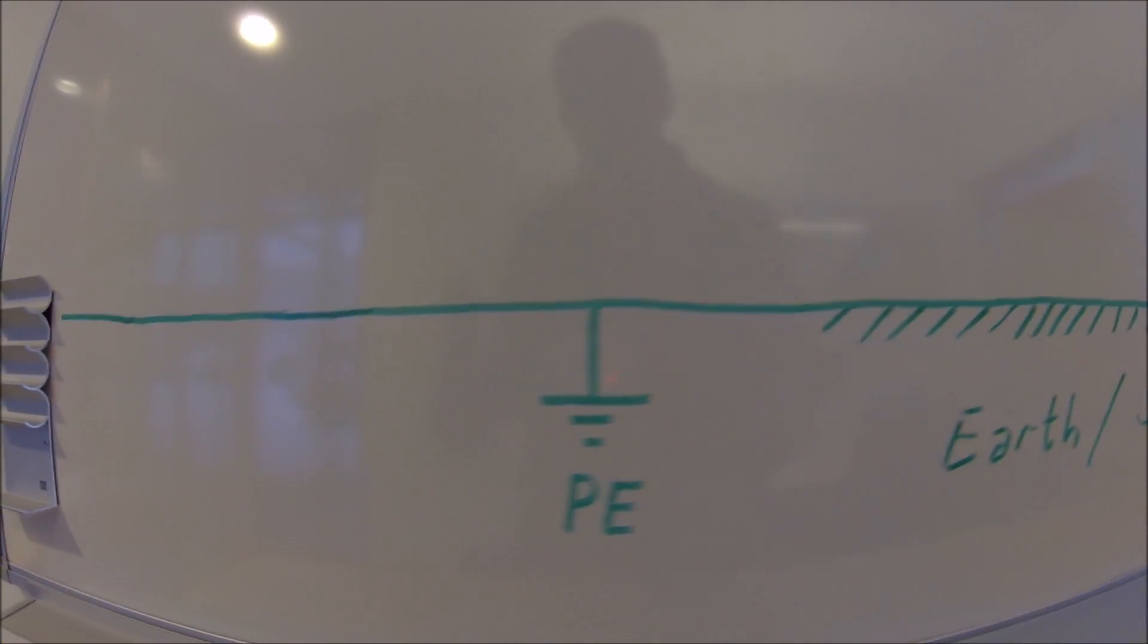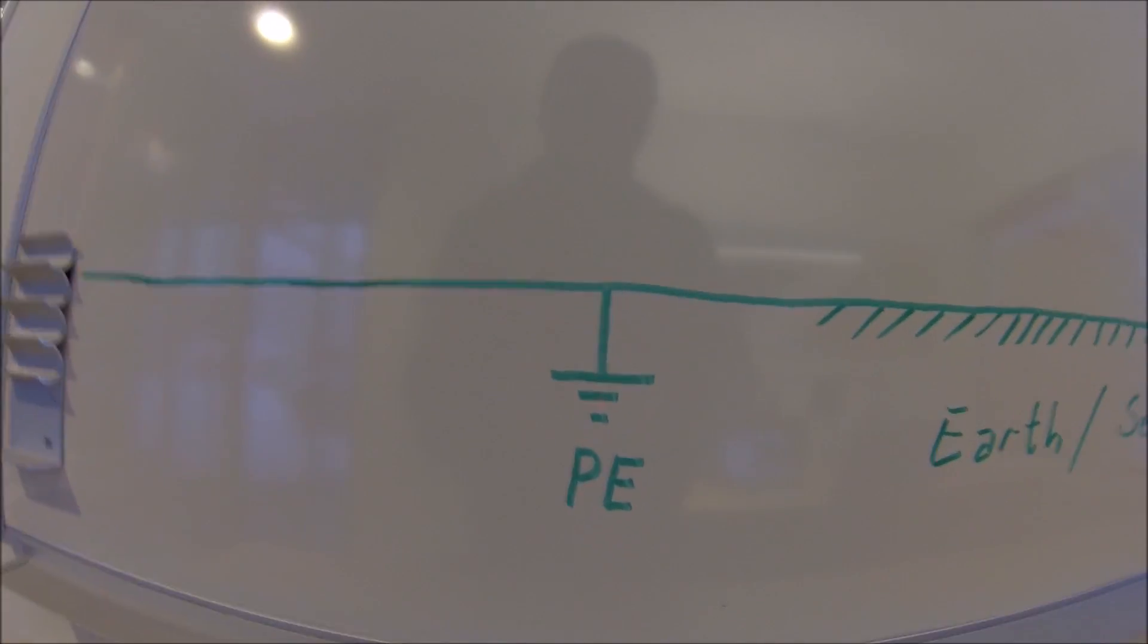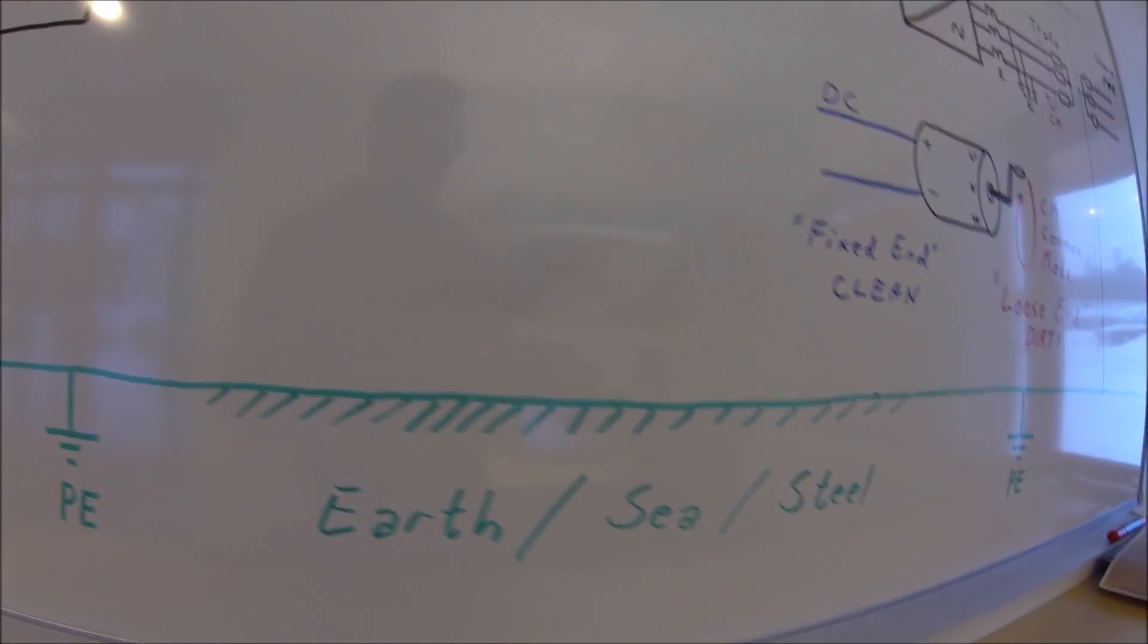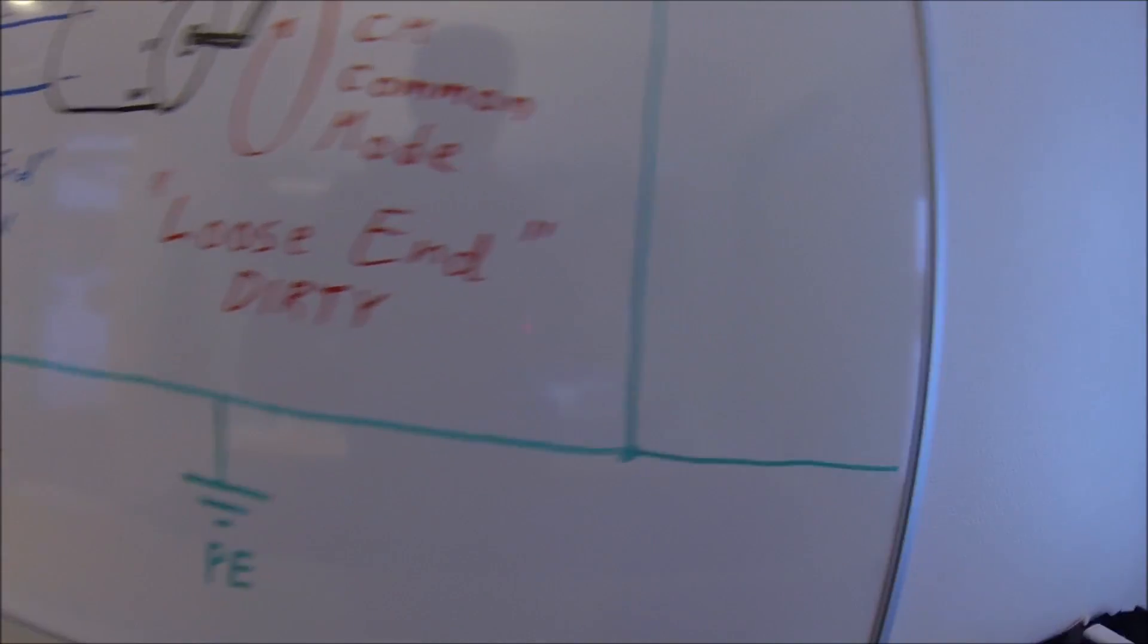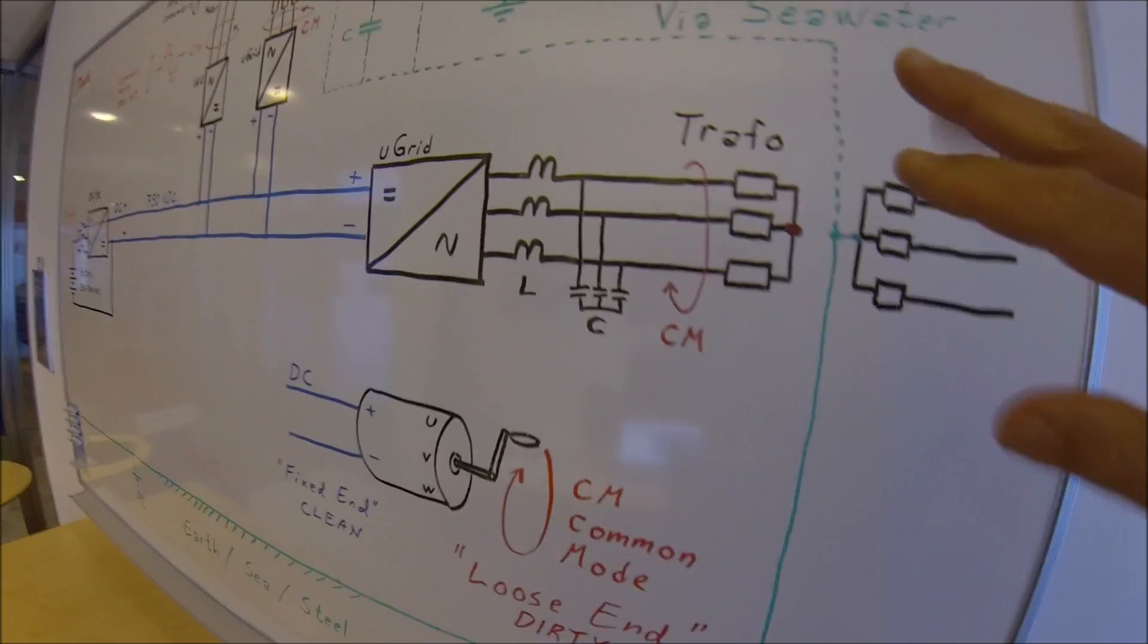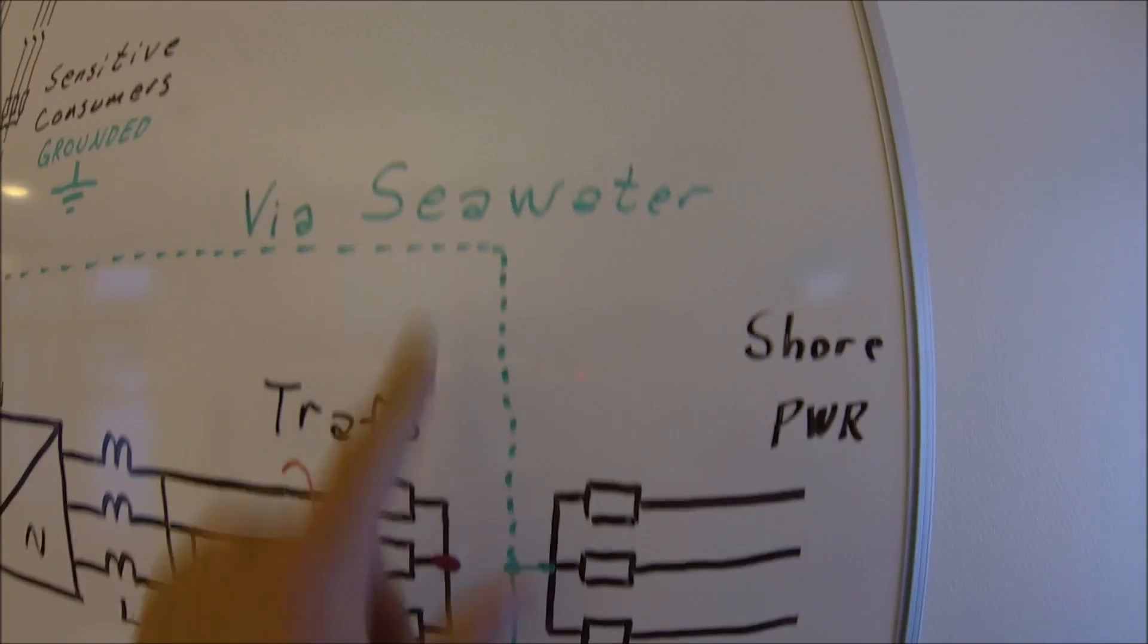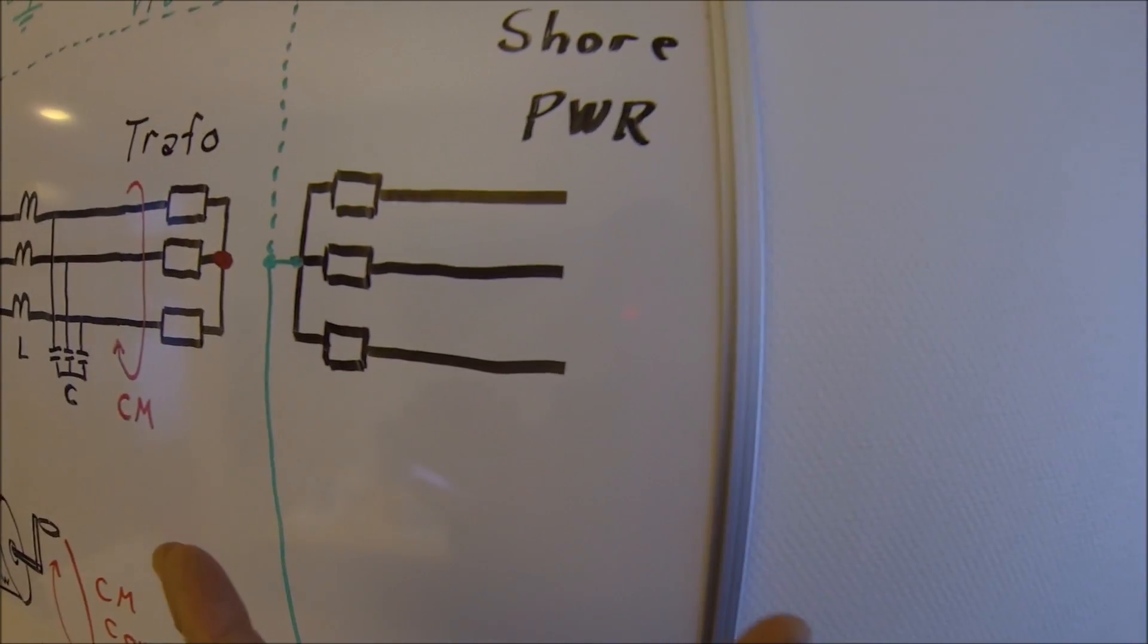The earth on board in a ship is so-called floating earth. But there will always be a capacitive coupling to all the consumers and also the steel will via the seawater connect it to shore.